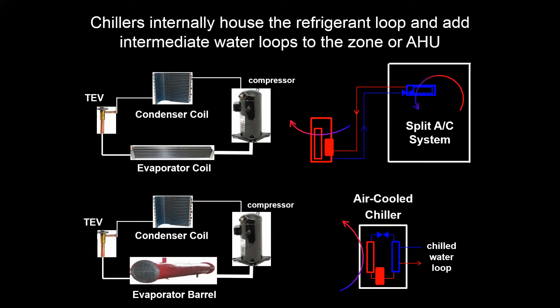Last time we looked at a simple DX vapor compression system and how it was split between components in the zone and components out in the ambient air. With a chiller, all of those four main vapor compression components are housed internally in one device called a chiller, that interacts with the chill water loop on the evaporator side and the ambient air on the condenser side if it's an air-cooled chiller.